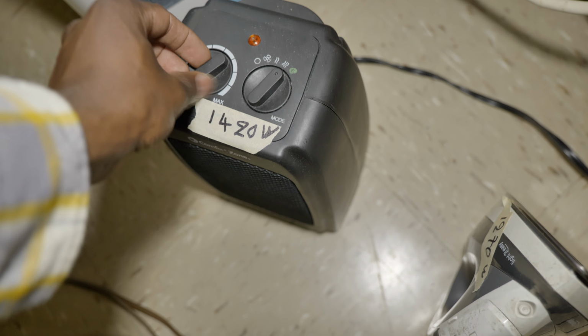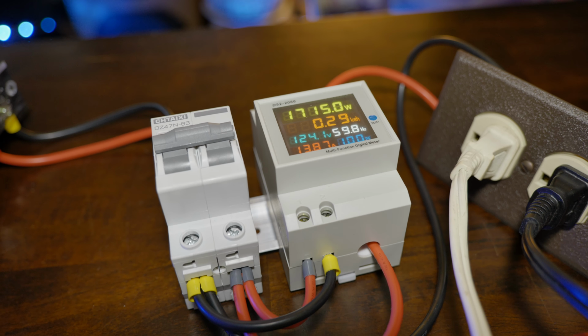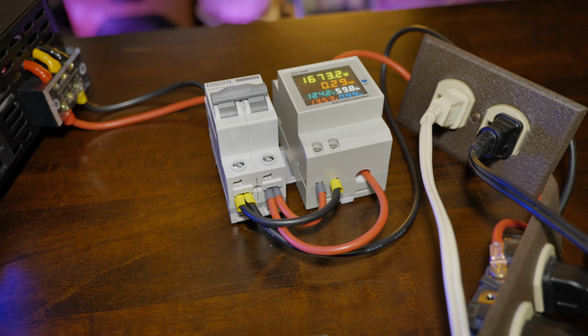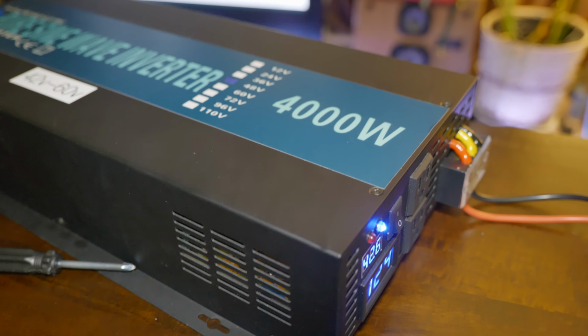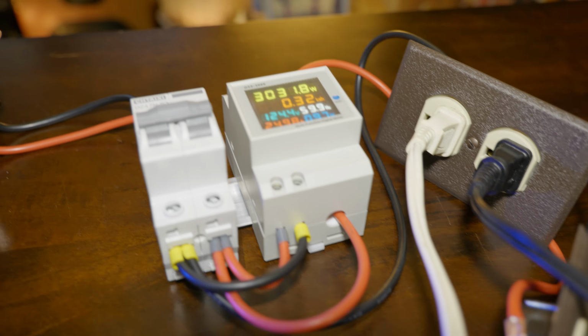36, 31, 32, then back down to 1700, 1700, 1600, and then the microwave kicks in at 30, dropped to 43 volts. So I'm gonna let it run for a little bit. This shows that it does try to hold up, but the voltage drop to 42 is not gonna help it, but it is running.